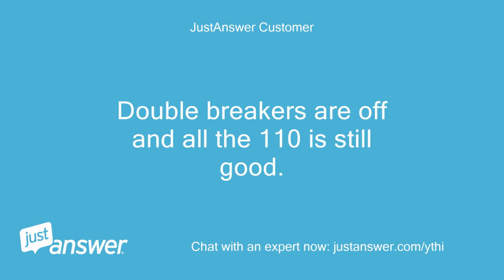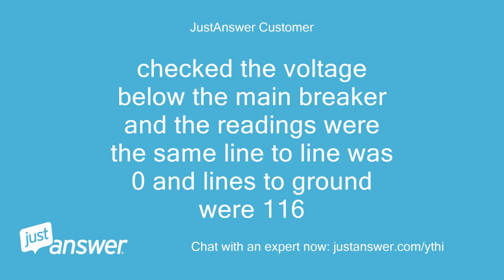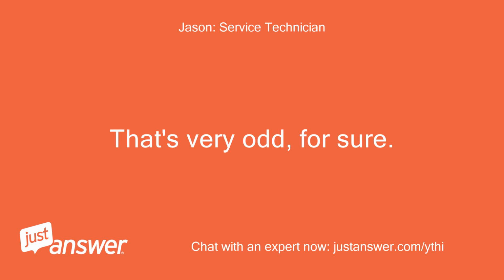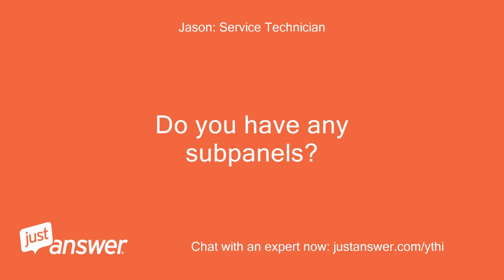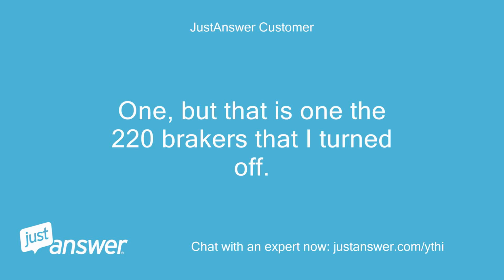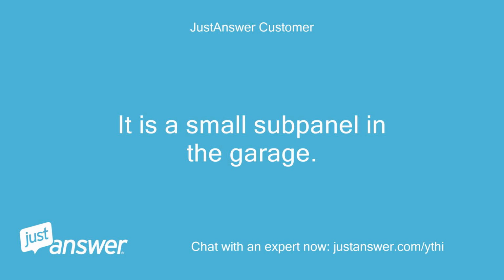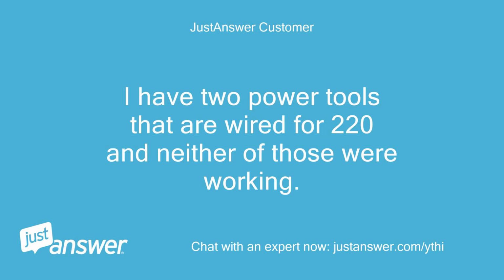Double breakers are off and all the 110 is still good. Checked the voltage below the main breaker and the readings were the same. Line to line was 0 and lines to ground were 116. That's very odd, for sure. Do you have any subpanels? One, but that is one of the 220 breakers that I turned off. It is a small subpanel in the garage. I have 2 power tools that are wired for 220 and neither of those were working.